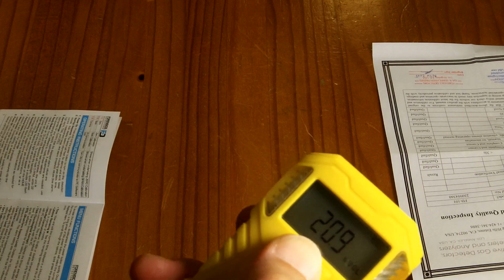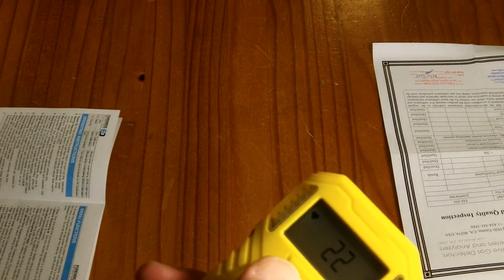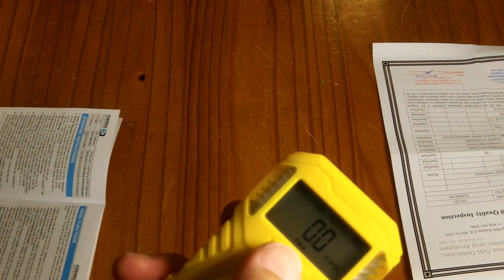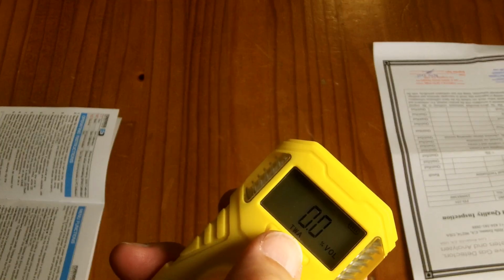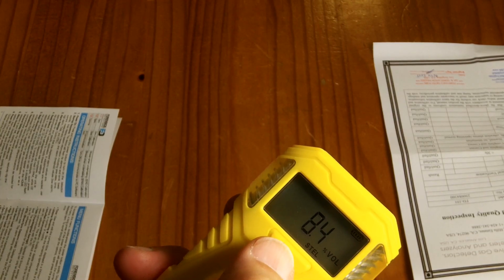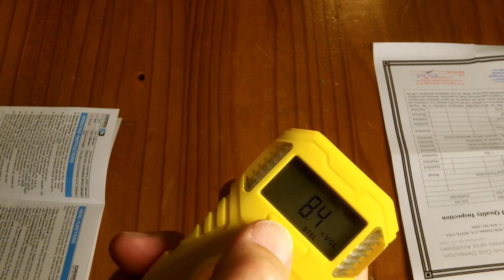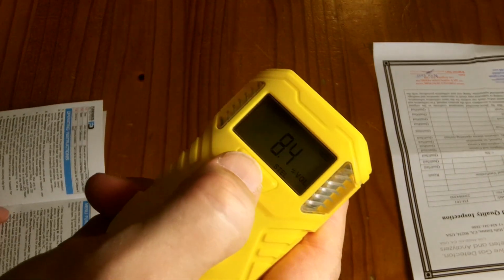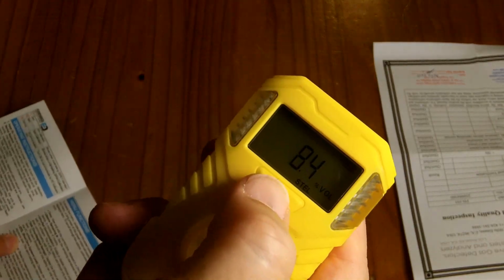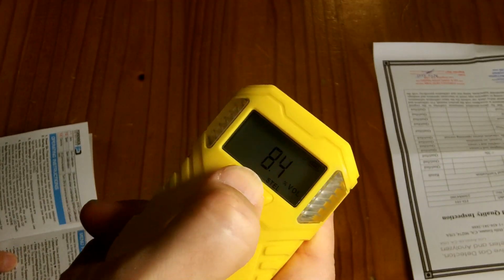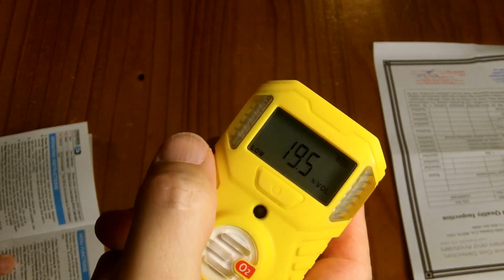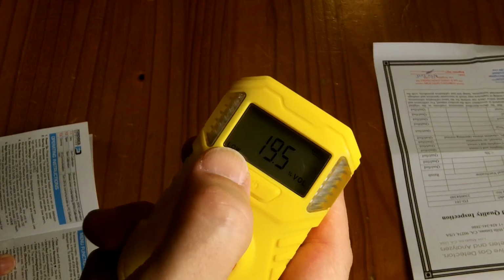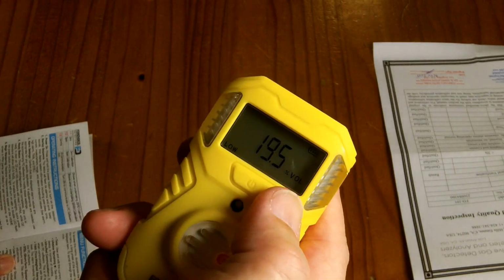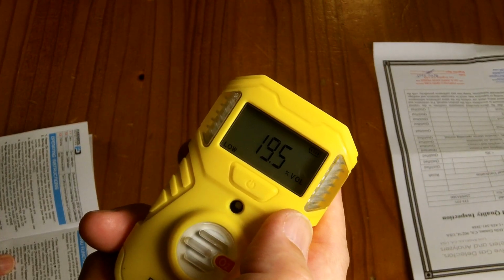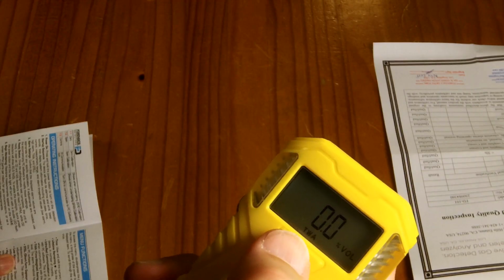So the built-in limits, we have here the time weighted average, and it's basically 0%. And then we have STEL, which is the short-term exposure limit, and that's 8.4. And then we have the low. And for an oxygen sensor, the low is really the important thing. It's 19.5. So anything below 19.5% oxygen is going to set off the alarm. So there's also a high setting.